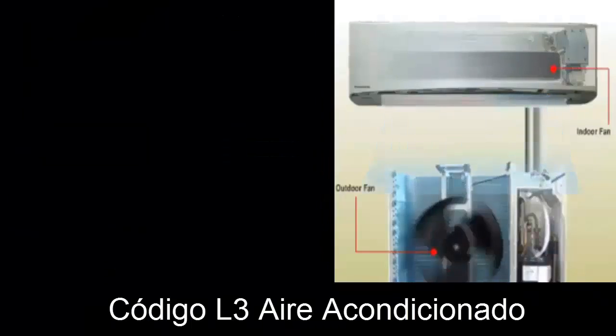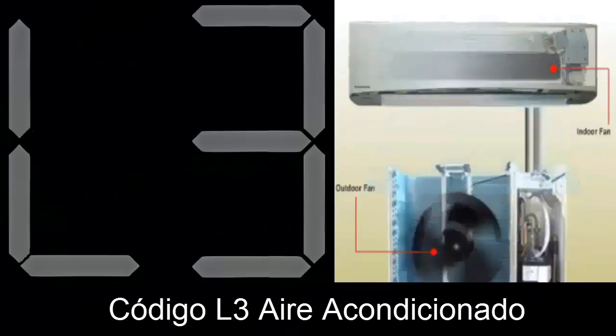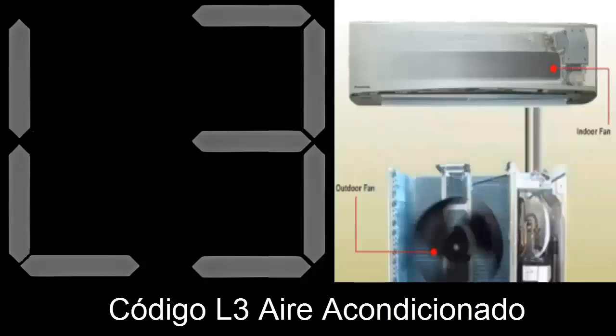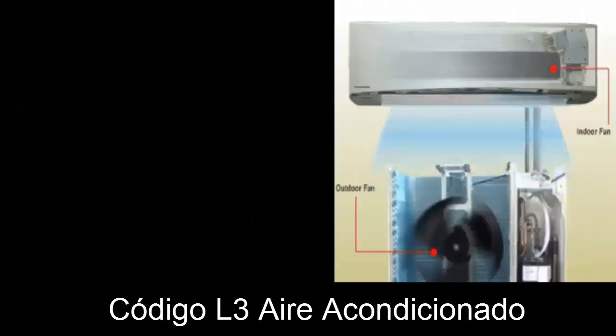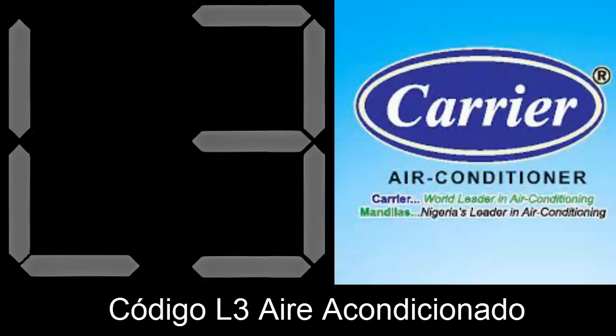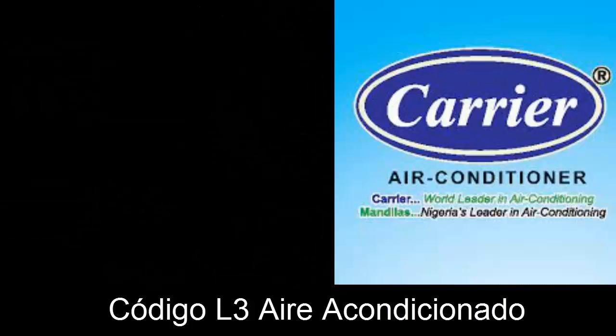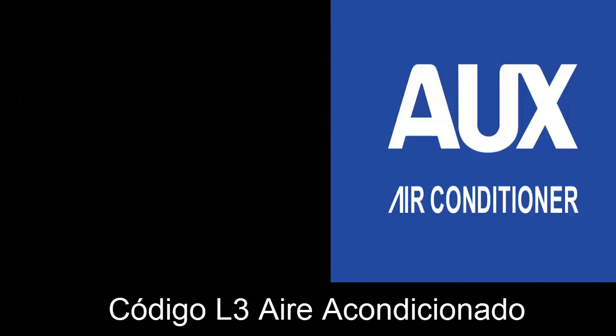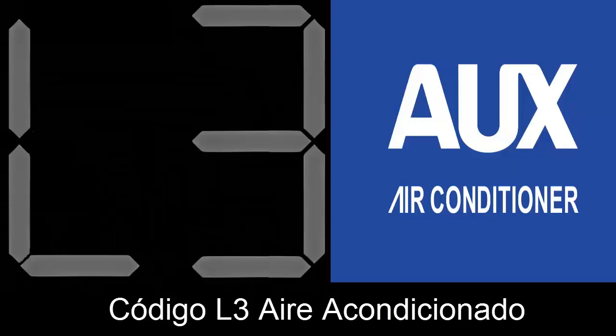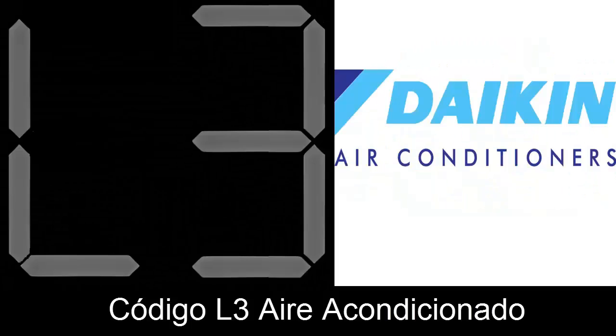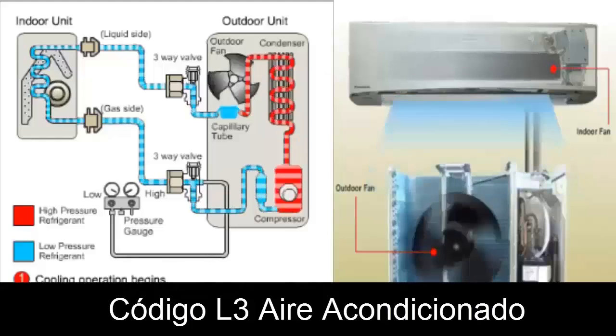Finally, it is important to note that for other manufacturers, the meaning of the L3 code can vary as follows. For Carrier, the L3 code detects overcurrent in one phase of the motor. For AUX, the L3 code relates to compressor protection. For Daikin, the L3 code indicates an increase in temperature in the electrical panel.